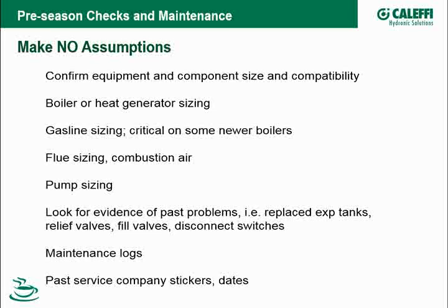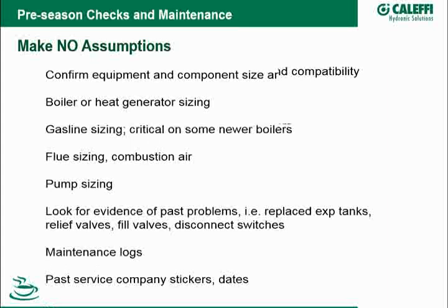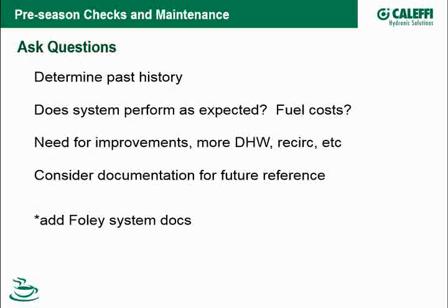And then again, I can't stress enough keeping some kind of documentation on the job. Sometimes what I would do, right on the front cover of the boiler, I'd just take one of those small Sharpie things and make notes right on there, the date that I was there and what I did, especially if I'm checking glycol and stuff like that, that somebody wants to keep an eye on yearly to see if the pH range or something's dropping, you know, they've got a problem coming up.